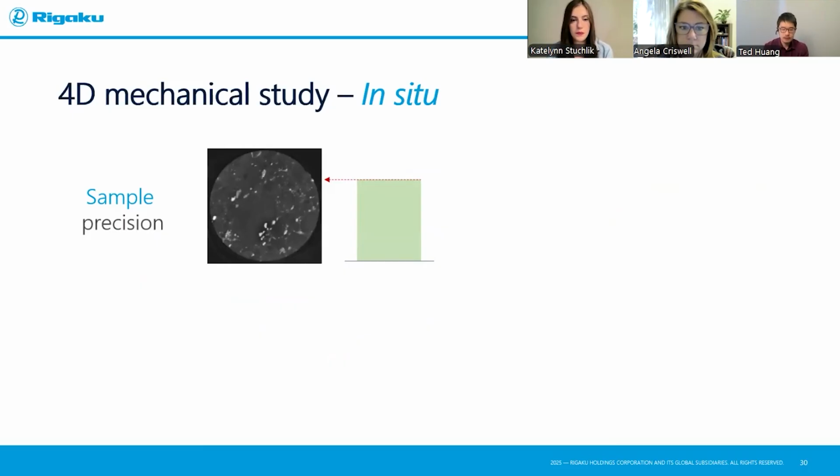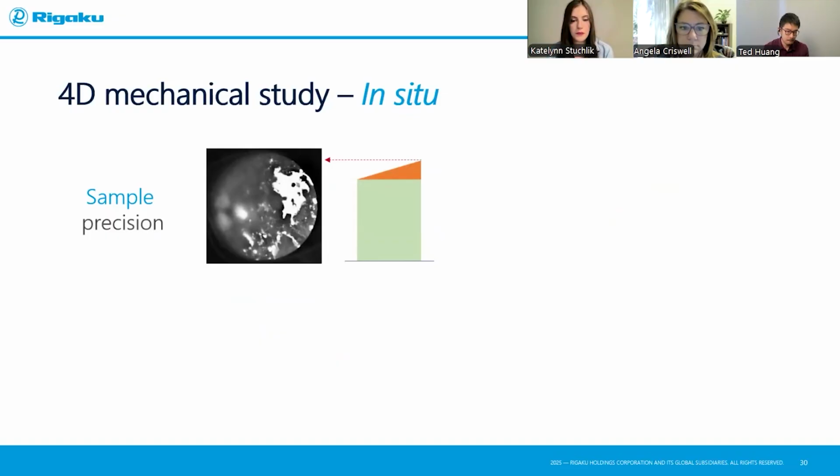I will see this cross-sectional image. Everything is in the field of view, not out of focus. If it's tilted, not flat enough, you will see something like this. You have a blur at the edge because that side is just out of focus when you're trying to look at the cross-sectional view.